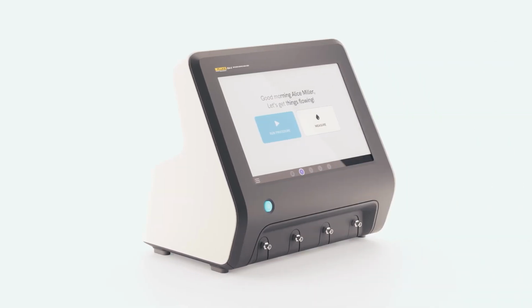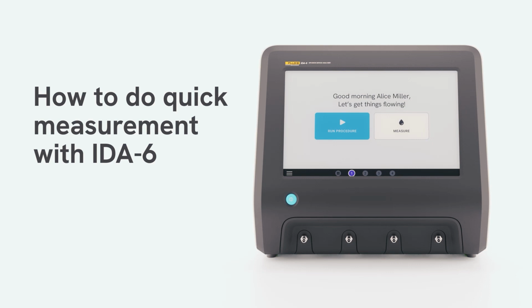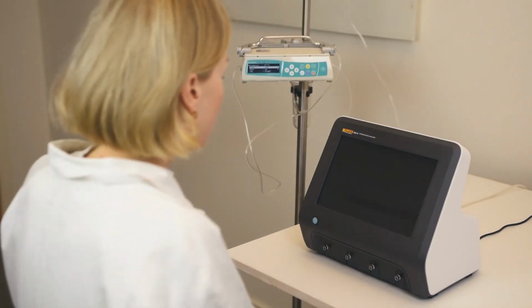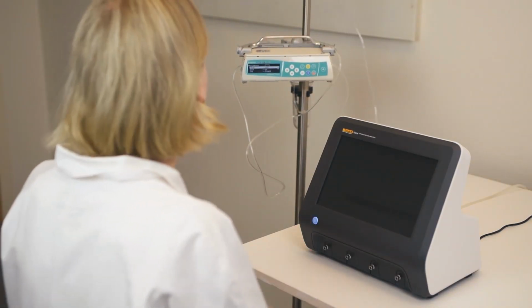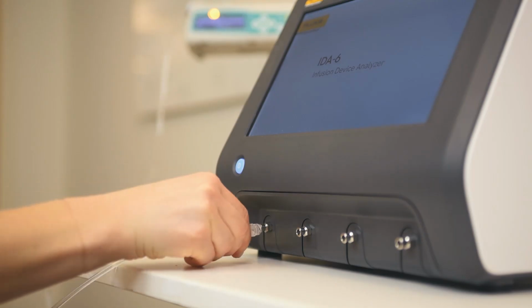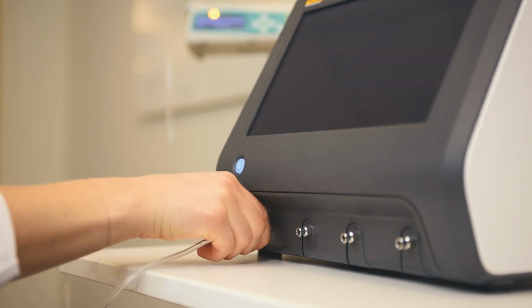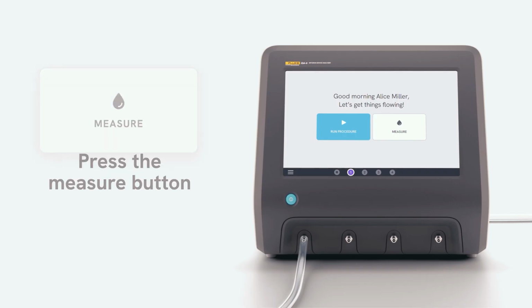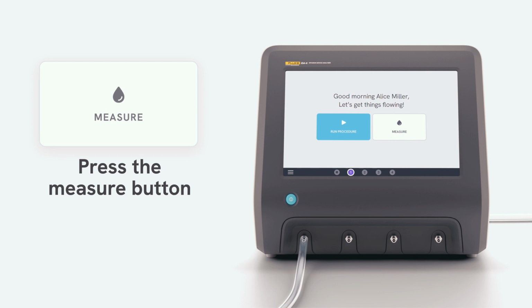Want to perform a quick measurement on IDA-6? Here's how you do it. Start by turning the IDA-6 on and connect your infusion pump to one of the channels. When everything is set up, go ahead and press the measure button on the home screen.